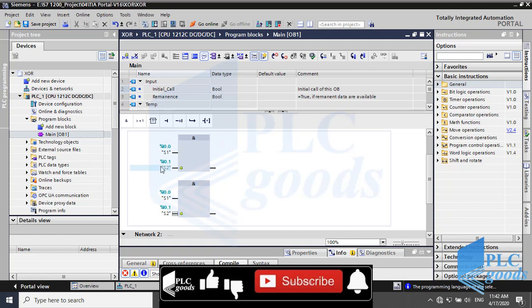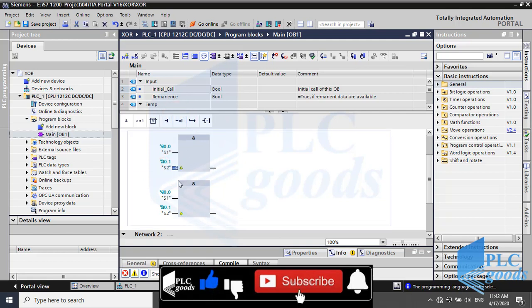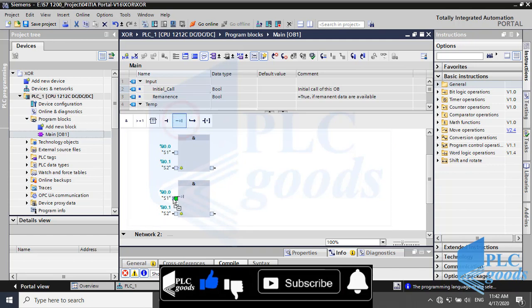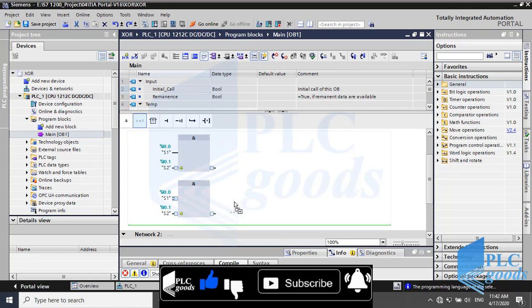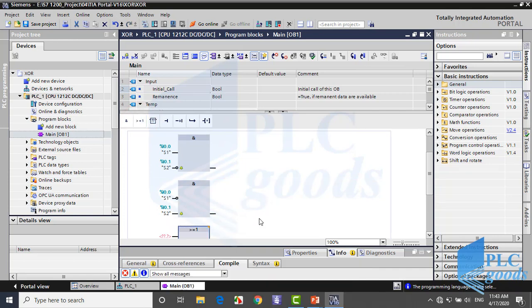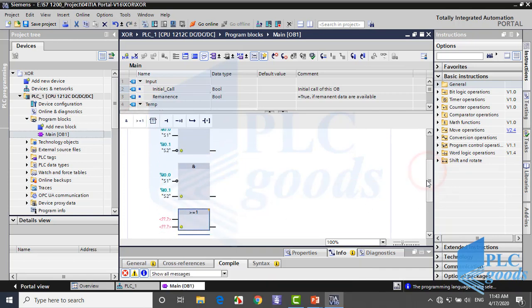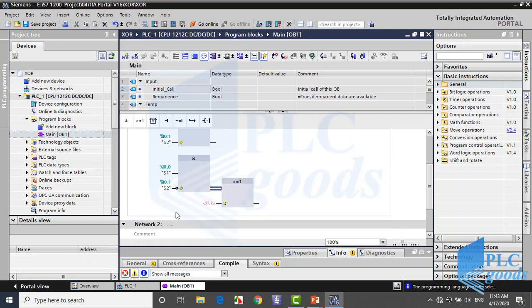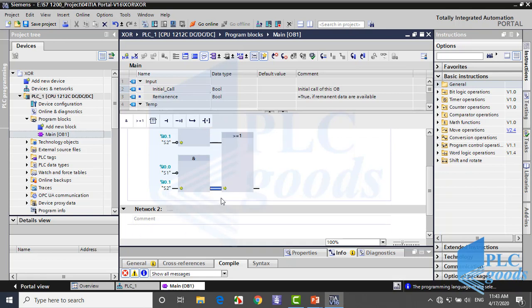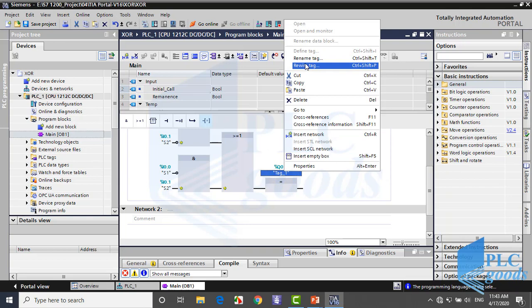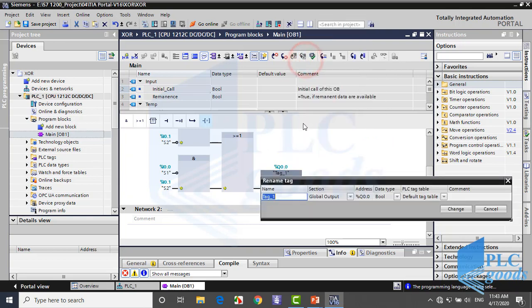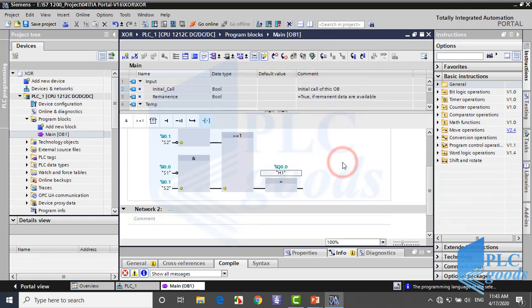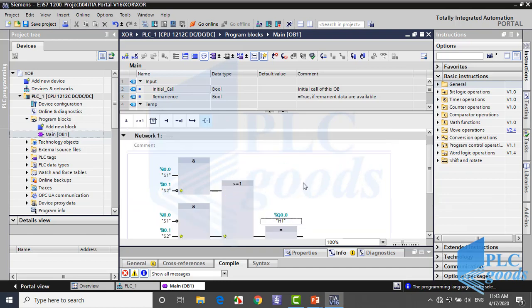Let me insert two AND blocks and define their inputs. Based on XOR logic, we must use this instruction to invert inputs. Now insert an OR logic and connect AND block outputs to its inputs. Now insert an assignment instruction to store RLO. Well, we've made an XOR logic.